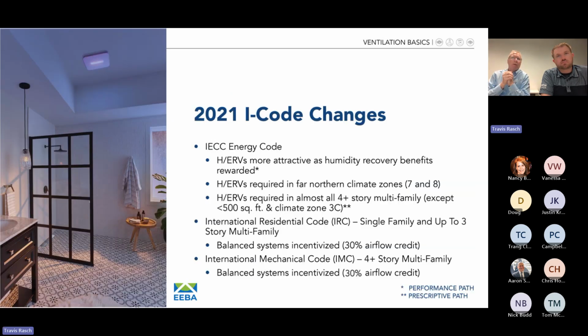So, 2021 code changes. This has probably been adopted by about 10 or 12 states now. One very important thing is they require that you field verify your dwelling unit ventilation airflows now. So it's very important to make sure you're putting in a ventilation device that's going to get the job done for the requirements, and that you duct it properly. Keep the static pressure low enough so when that HERS rater comes and checks, you can be comfortable that you're not going to get red tagged.